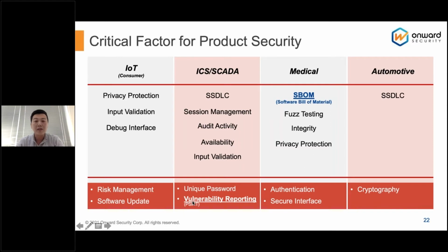And for medical devices, privacy protection is also quite important. But for the FDA requirement, they have a special requirement about the software bill of materials. Because once your device is released to the market, the FDA requires medical device makers to continuously monitor those software components, including the open source libraries used in your product. You need to continuously monitor those libraries for new vulnerabilities. If you find a new vulnerability, you need to release a patch or software update for your medical devices.